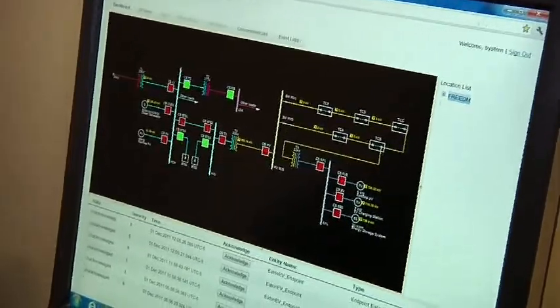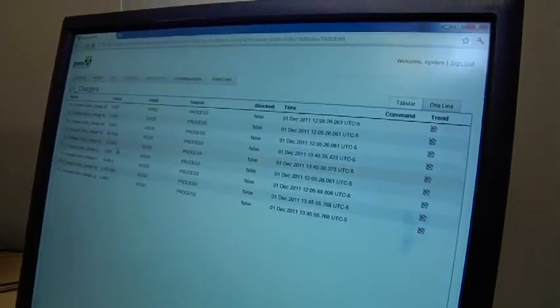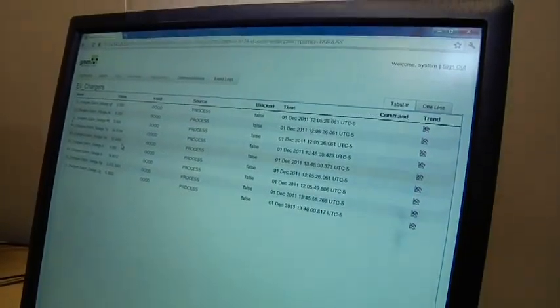Of the lab. Okay. There's the EV charger outside. Oh, okay. So actually, that's the data we're reading from it right now. So the charger that the Volt was parked up against wasn't delivering power, but the one on the wall behind it was. Okay. And that would show up here? That would show up. One of the issues that you have with any of this new smart grid stuff is it's not quite all ironed out. You'll find some of these chargers coming from different manufacturers don't have communication ports on them, that type of deal. So the one you were charging off of actually did not have communication support.